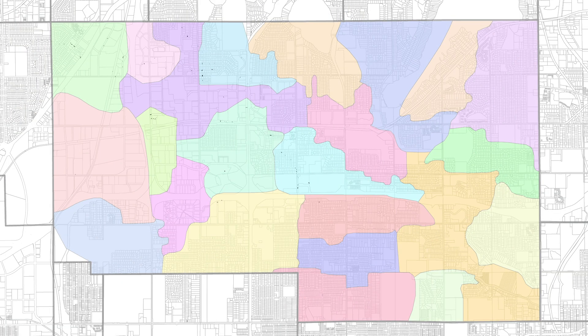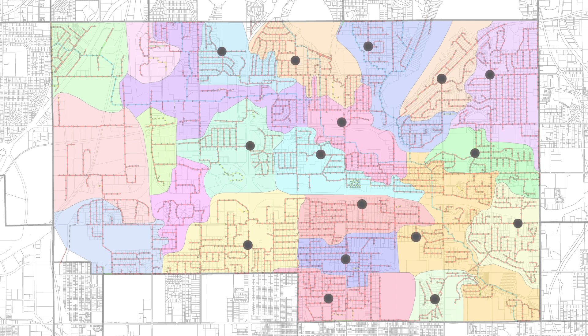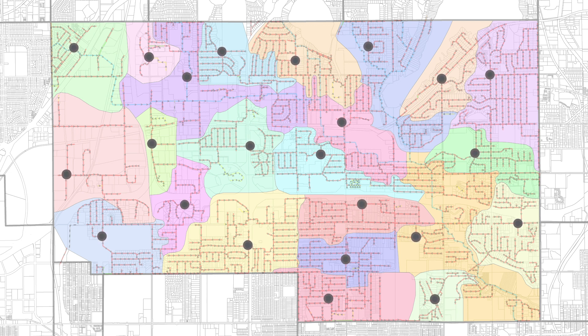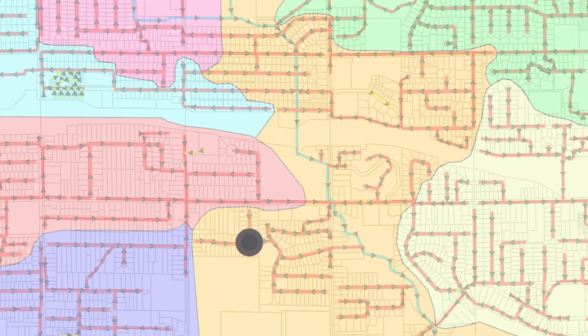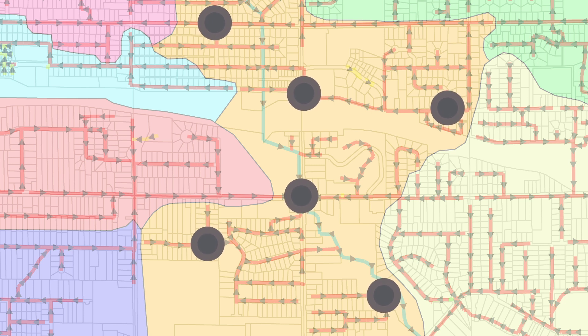Say we've broken down a city into ten districts, so ten flow meters. We'll break that down and say, District 1 had one flow meter down here — we'll put in maybe five more, depending on how everything flows. It's kind of like a river system, so you go to the tributaries and work up to find where the issue is coming from. Then you can say, okay, meter 1-4 is where all the issues are.